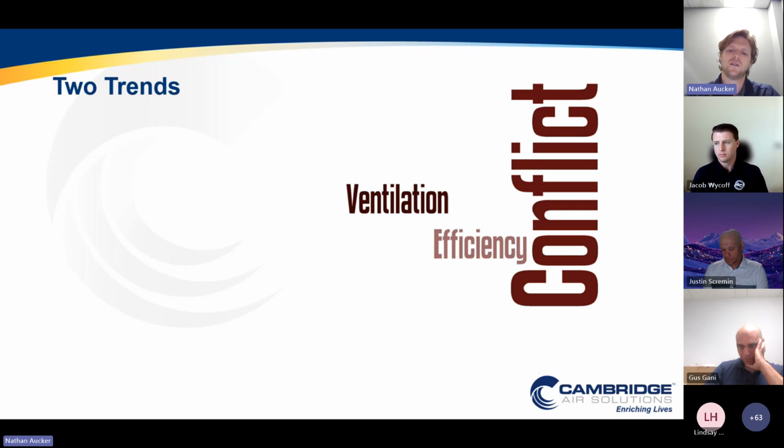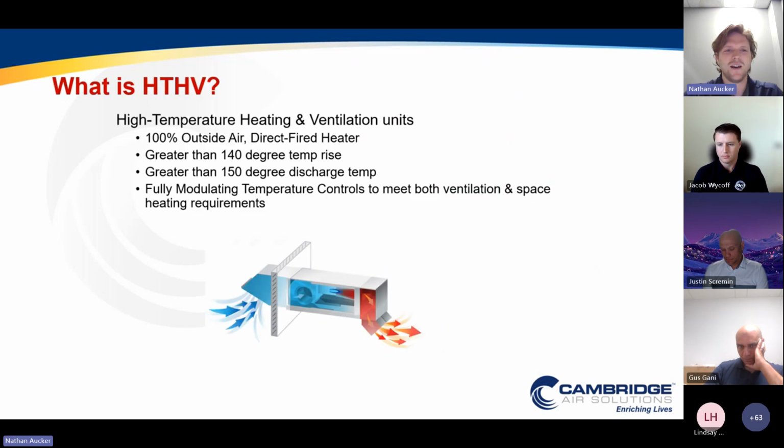So as we think about what that could be, we'll jump over to a technology called HTHV, or high temperature heating and ventilation units. For those who have not been in the large warehouse, distribution, or industrial space, it could be a new technology to you. That's great. That's a great place to be. A lot of opportunity. So what is HTHV? It's defined by the HVAC industry as a 100% outside air, direct fired heater with performance criteria of greater than 140-degree temp rise, and also greater than 150-degree discharge temp.